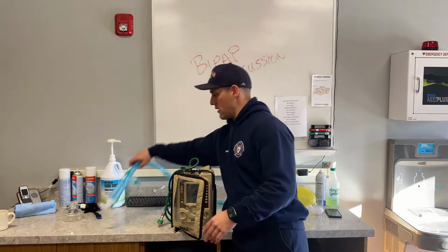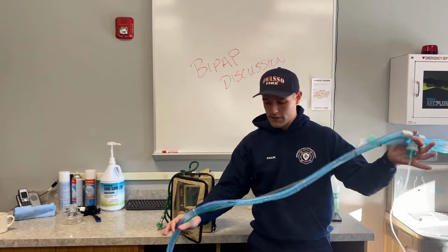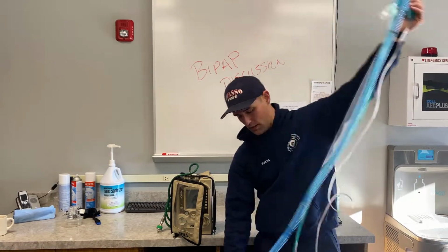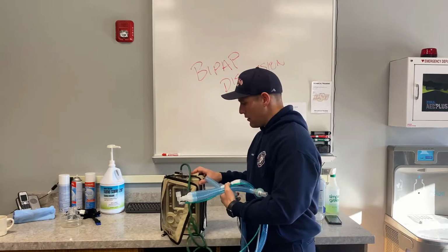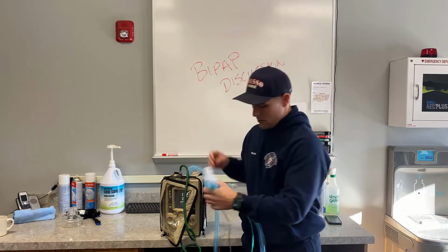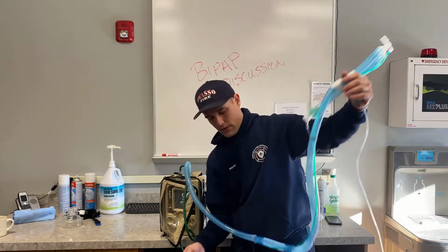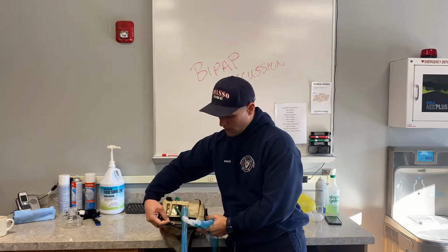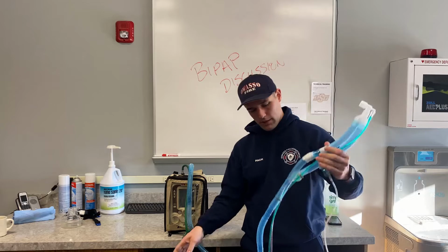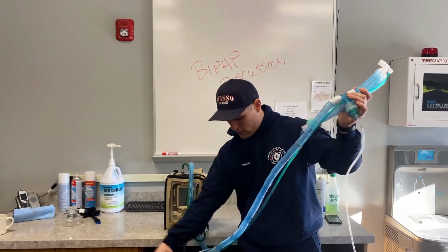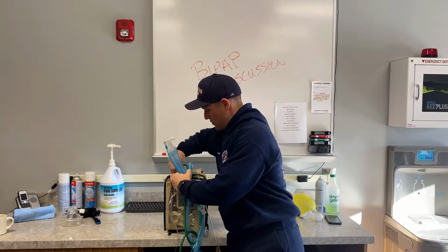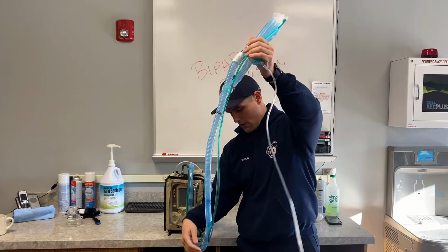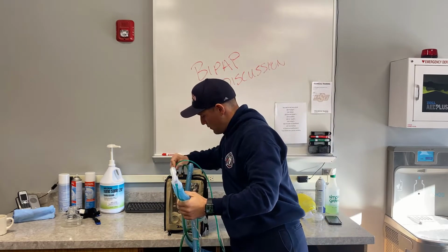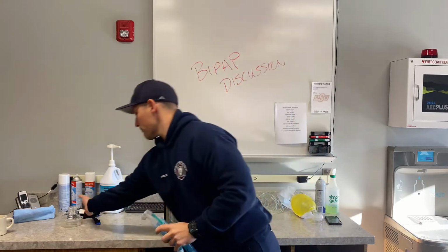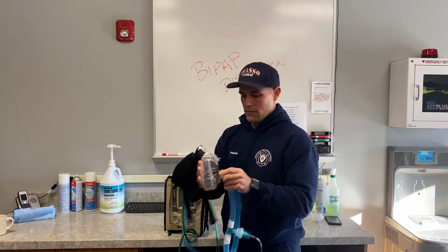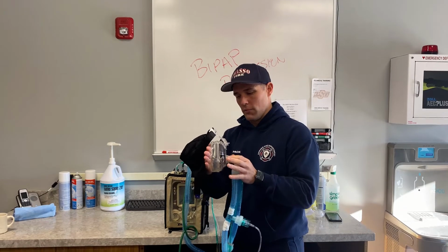Okay, so how I like to start is make sure I actually hook up the vent circuit correctly. We all know what the big tube is and where it goes, right there. What I've screwed up is the exhalation tube and the transducer. I've screwed that up a couple times. Some of the older vents may not be colored, but they do have helpful little pictures. What I like to start with is I grab the exhalation tube and I just go and put it on. And grab, there it is. O2 tube. All right, and then mask. Try to get a good seal on your patient.